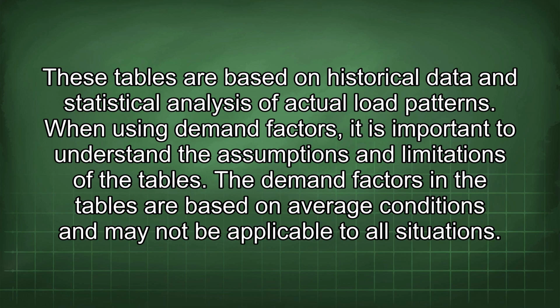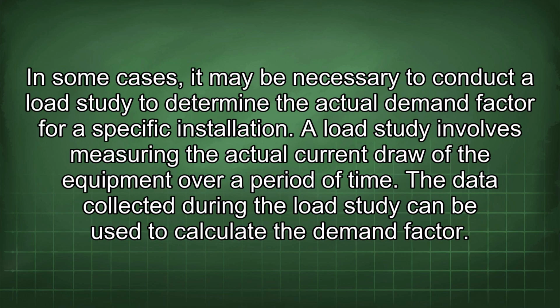The demand factors in the tables are based on average conditions and may not be applicable to all situations. In some cases, it may be necessary to conduct a load study to determine the actual demand factor for a specific installation. A load study involves measuring the actual current draw of the equipment over a period of time. The data collected during the load study can be used to calculate the demand factor.